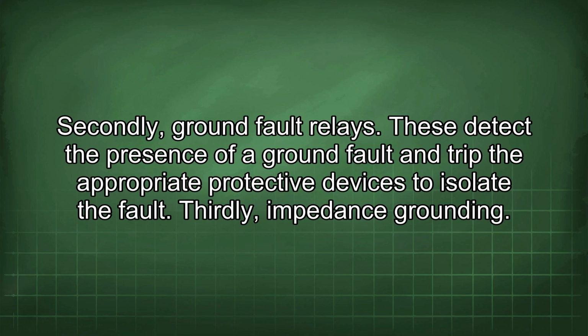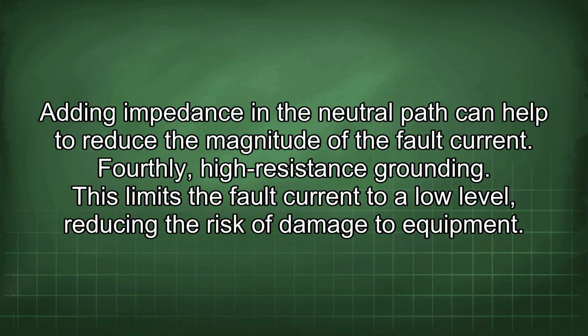These detect the presence of a ground fault and trip the appropriate protective devices to isolate the fault. Thirdly, impedance grounding. Adding impedance in the neutral path can help to reduce the magnitude of the fault current. Fourthly, high resistance grounding. This limits the fault current to a low level, reducing the risk of damage to equipment.